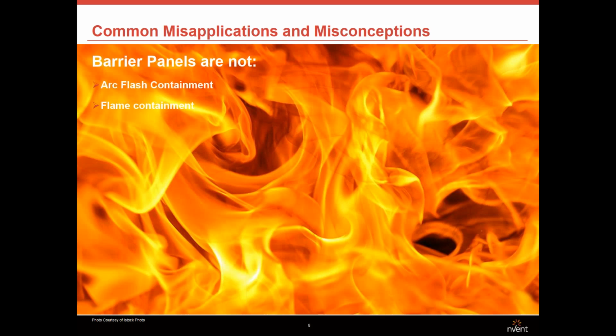Barrier panels are not flame containment. While the barrier panel does provide a physical separation between the bays, depending on the construction of the barrier panel, there may be small holes in the panel. And if there is fire in one of the bays, that fire may spread to another bay in the enclosure. So it's not total containment, it's just going to be deflection.